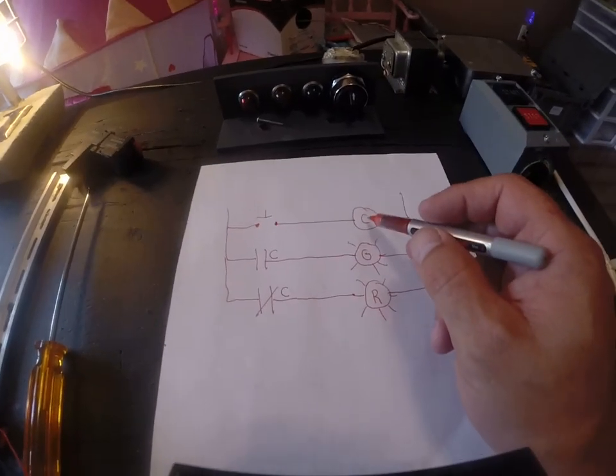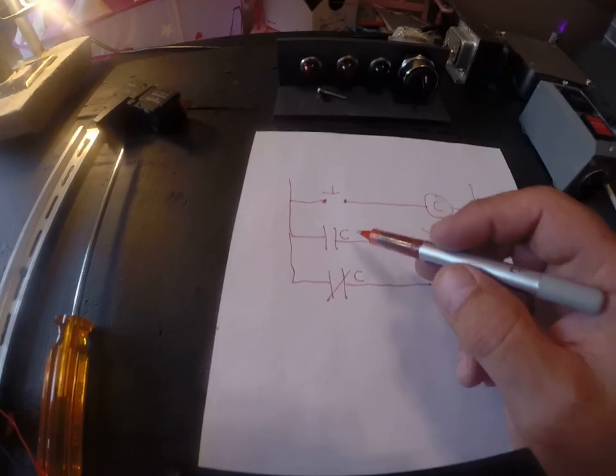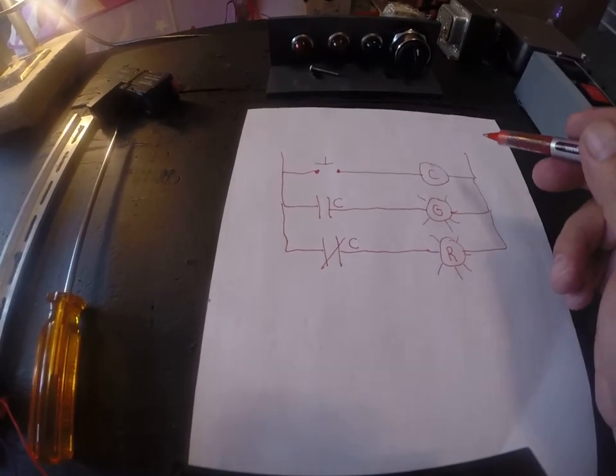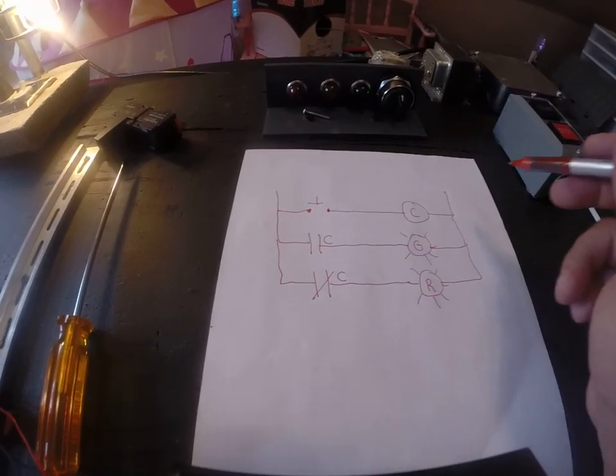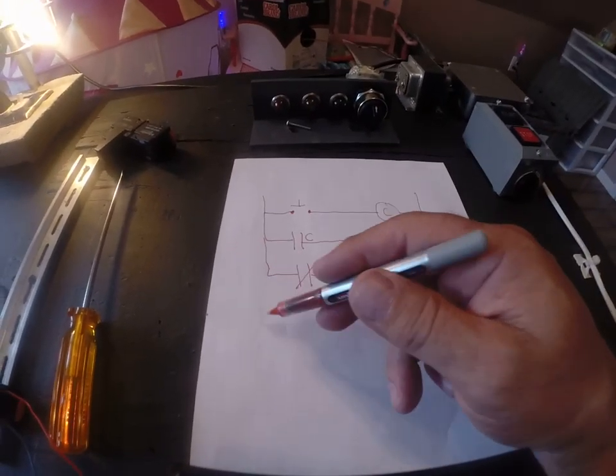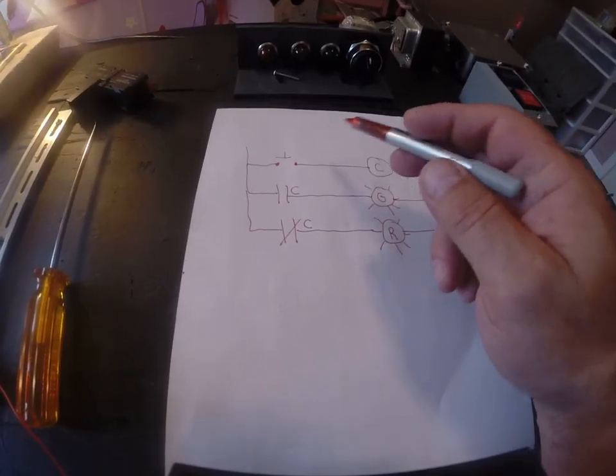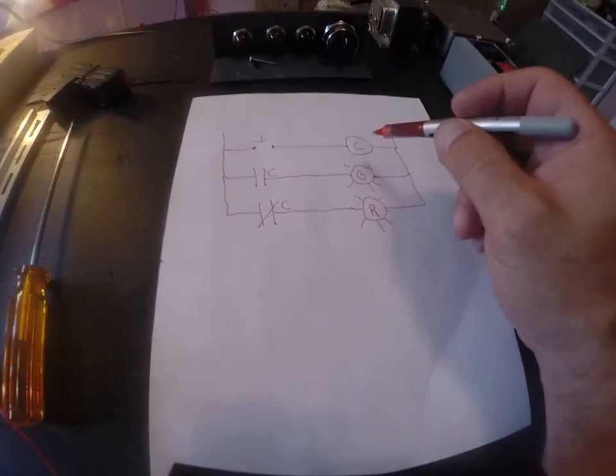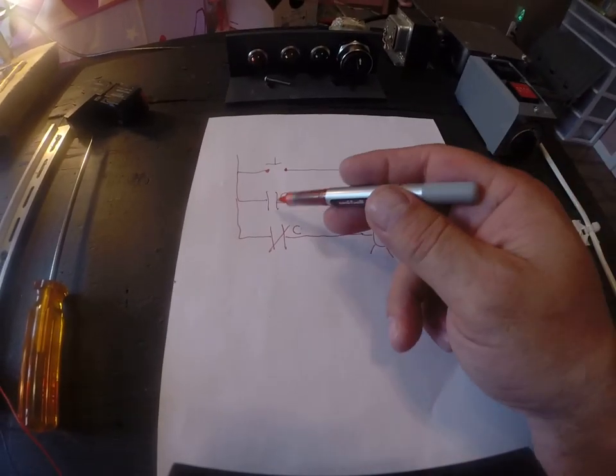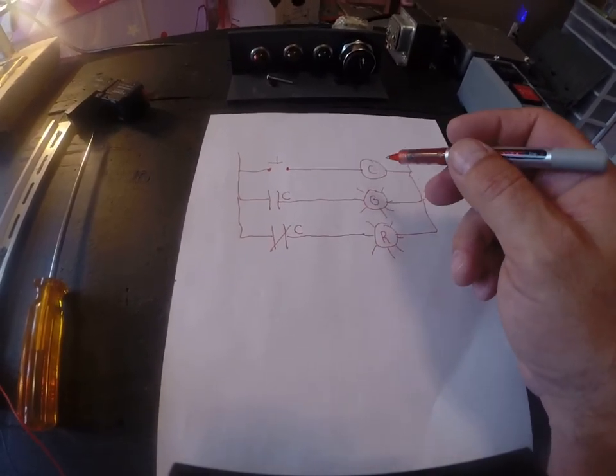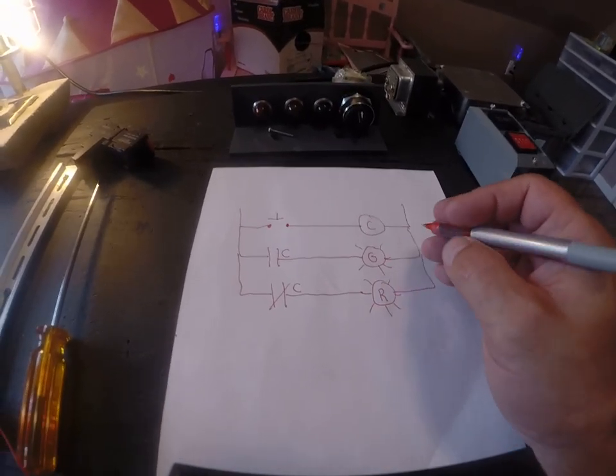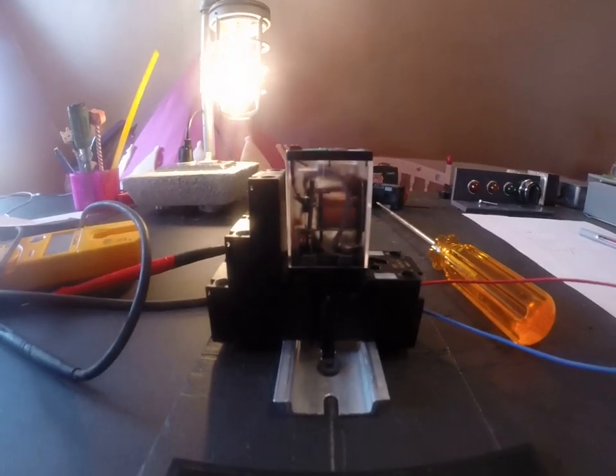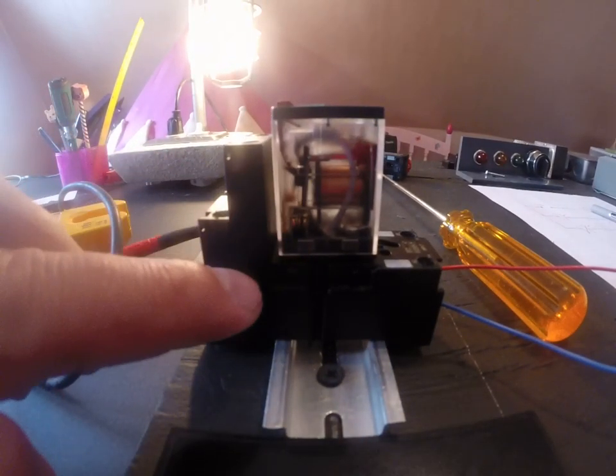And this relay being called C, well, it controls this contact and this contact all by the press of one button. And I could increase this by another set of contacts of each. So in reality, by me pressing this button and energizing this coil four different things could happen or more depending on how you wire it. So that would kind of be the diagram for that. And we're looking at it right in real time. We're seeing this action happen.